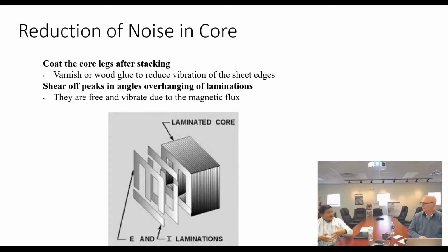So in the last few slides, we discussed how we clamp the core structure tightly to make one homogeneous structure, a kind of solid mass, where there is a lack of air gap and a lack of free or vibrating elements, and that will help us reduce the transformer noise. The whole core structure is uniformly pressurized at every point, and all these things help reduce the noise created by the transformer core. So that one component is now isolated or improved, and then there are other components we're going to talk about next.